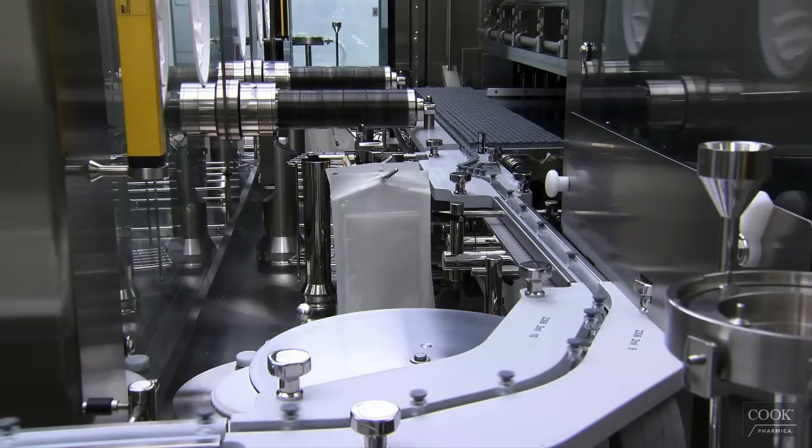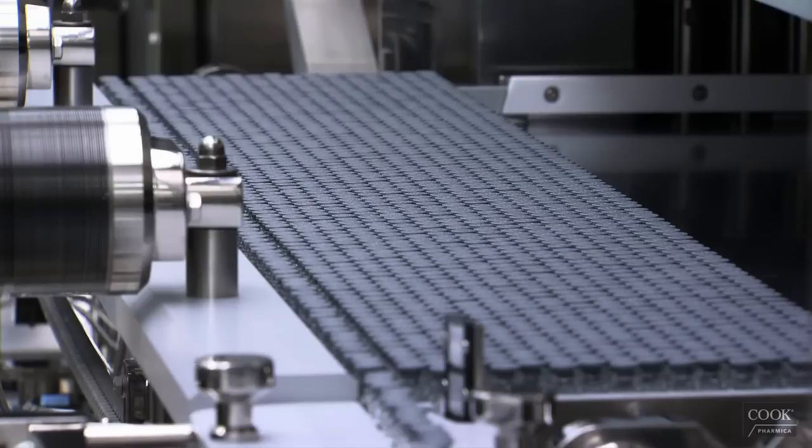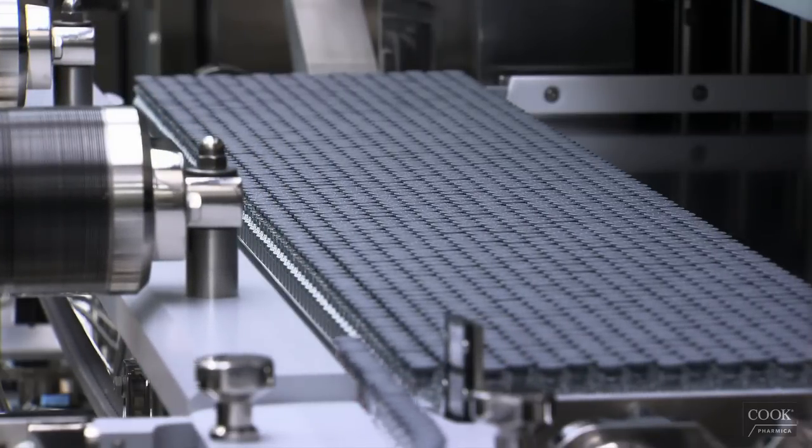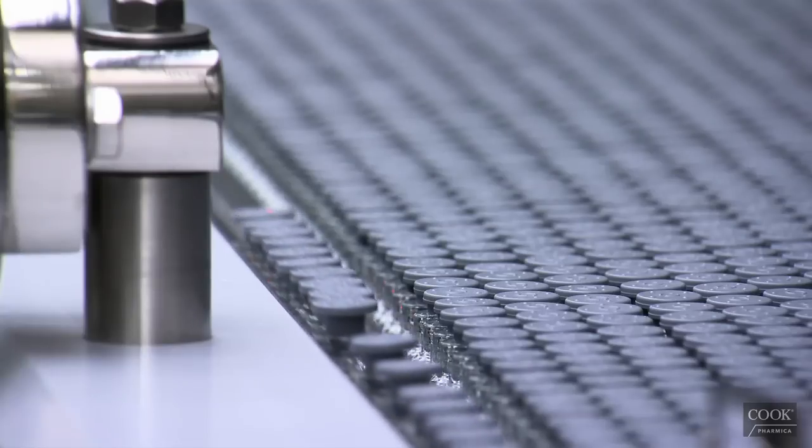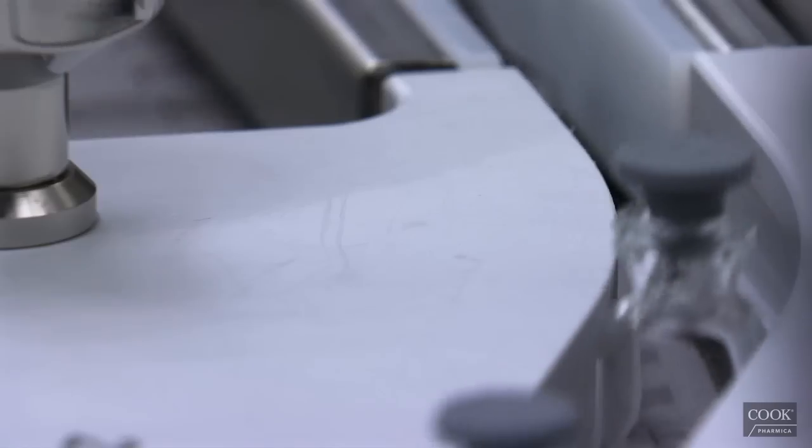For freeze-dried products, the vials enter the 250 square foot lyophilizer using an automated loading and unloading system that feeds vials row by row. The lyophilizer can hold 120,000 2-milliliter vials or approximately 30,000 20-milliliter vials.